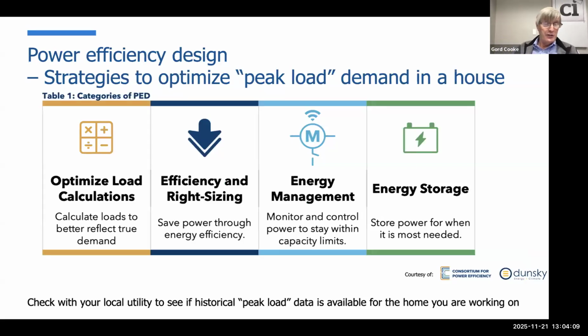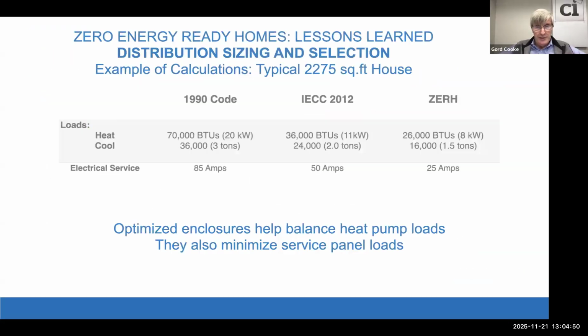First and foremost, on the left is optimize load calculations—do the proper sizing. Second, in the middle, save power through energy efficiency—build a more energy efficient house, use heat pumps that use less energy and at less peak load. Third, once you've done those two things, could you monitor and control what we'd call peak shaving or load shifting? And lastly, could we use energy storage? These are more or less in order of complexity, simplest to do first—start on the left, get that done right, and work your way to the right to see where we need to end up.